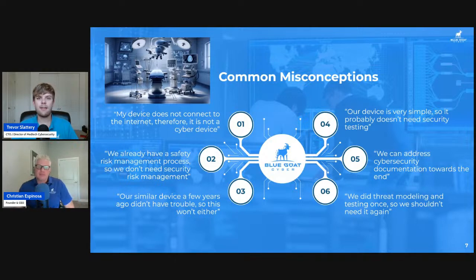And I think as an industry, the medtech space is getting better about addressing cybersecurity early, but it's still an important issue that we need to cover, and we need to make sure that manufacturers and medtech innovators are aware that this is something that has to happen early. Regulatory affairs professionals need to make sure that manufacturers are getting their documentation in line towards the start of the process instead of pushing it all the way towards the end. Another thing we'll hear is, well, we did threat modeling and testing once, so we shouldn't need it again. This is an iterative and cyclical process. You can't do it once and say it's good. It should be continuous, as the device is going to constantly evolve, and so is the threat landscape.